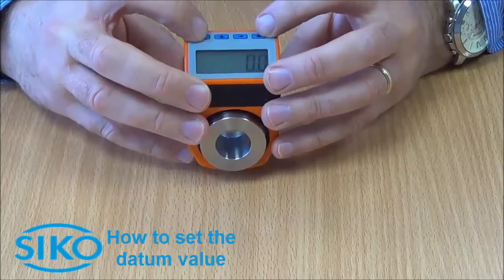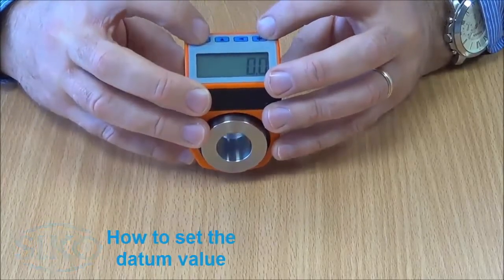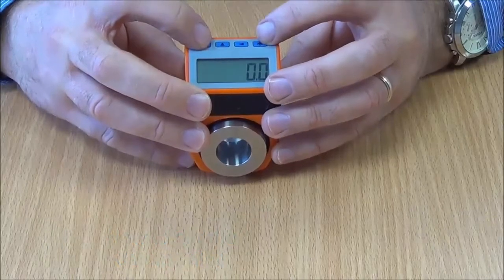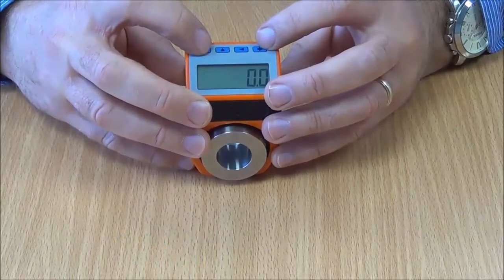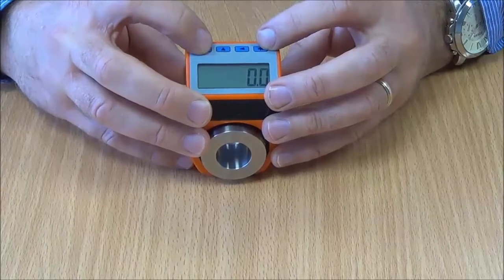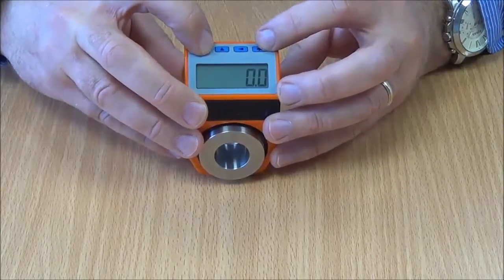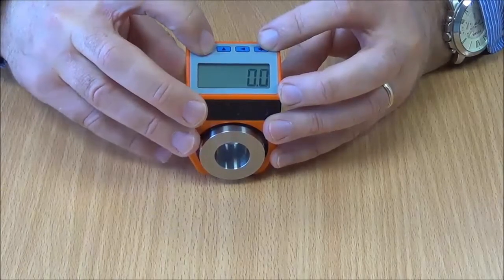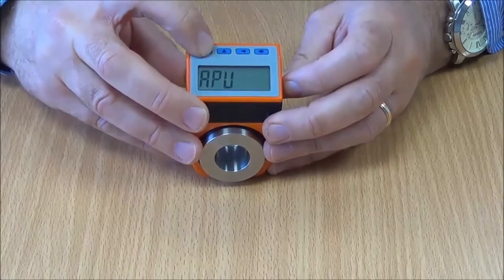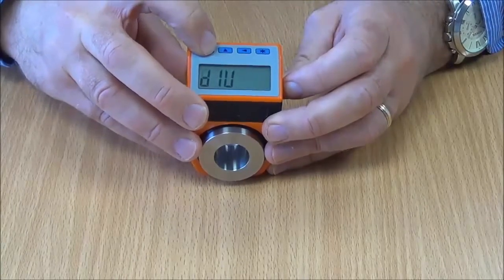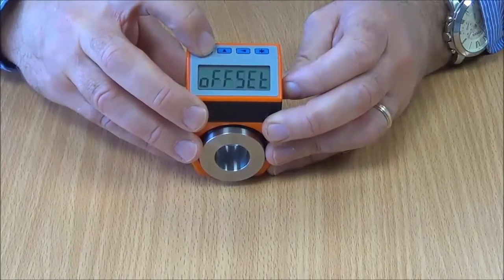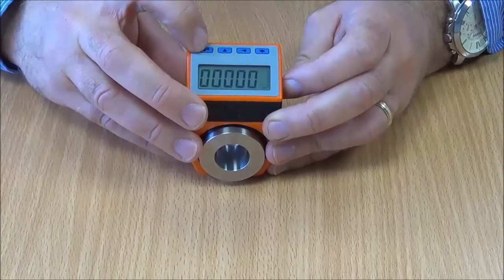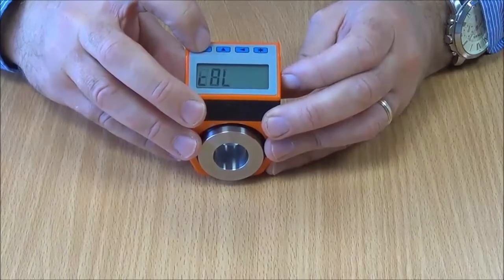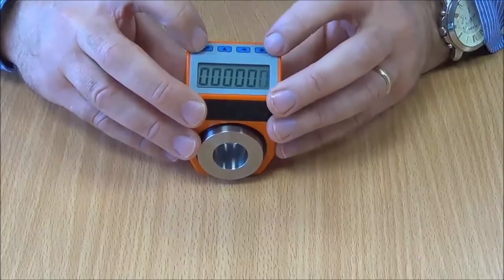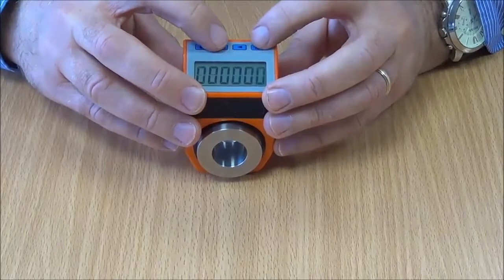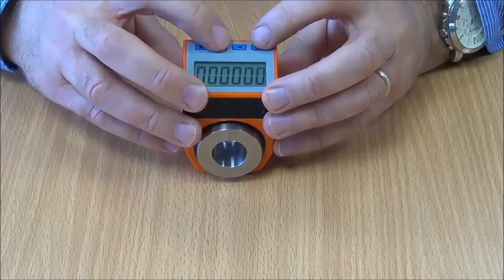This video will show you how to set the datum value, or what we call a reference value, on the indicator. You go into the programming mode via the P button for 5 seconds, enter the parameter list, and step down till you come to the setting shown as a calibration datum or reference value. This is normally called the absolute calibration point on the machine.